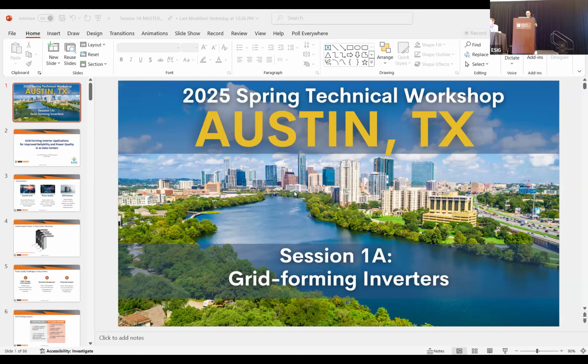If you look at the blue curve here, this is the type of ride-through that I'm looking for. I don't want to see overshoot of the voltage. I don't want to see undervoltage or anything like that. So grid forming can beautifully provide that voltage support and ride-through. One of the reasons I'm saying it's better to have the grid forming on the medium voltage side is the fact that all those UPS devices do not want to see voltage fluctuation. So that's the best place to fix everything, on the medium voltage rather than the high voltage.